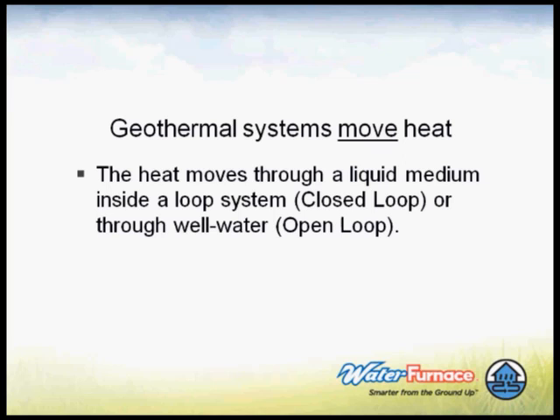We actually have an environmentally friendly freeze protection inside that closed loop. The reason for that is not so much the risk of it freezing in the ground, but because we can get heat out of 28-degree water. We can actually extract heat from water that's only 28 degrees, and when we return it after taking that heat out, it's even colder as it goes through the system. That's the main reason for the freeze protection, if that makes sense.